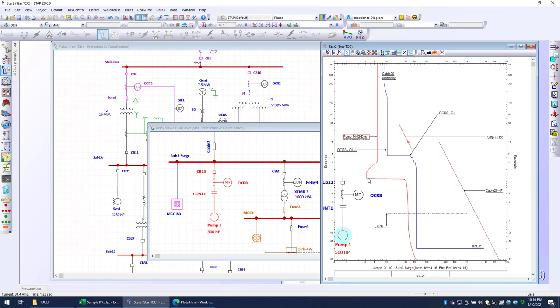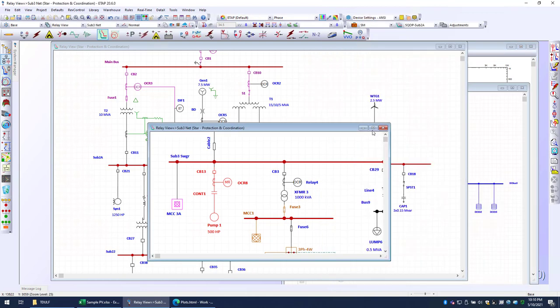The motor starts. Right here, there's a small delay of about 1 second, and it begins to ramp up from 40% loaded to about 90% loaded. Then the motor starts. So once you have this, you'll notice that you probably have some adjustments to do on your protection. So I just wanted to highlight how easy it is to perform a dynamic motor starting and put that information into protection and coordination. Next, I'd like to go over harmonic analysis.